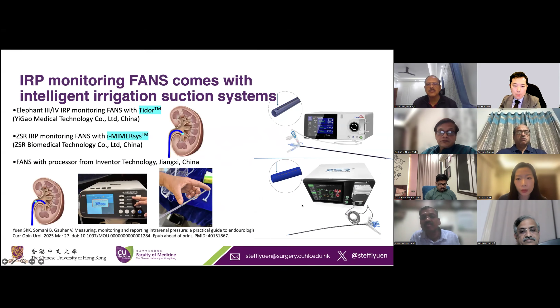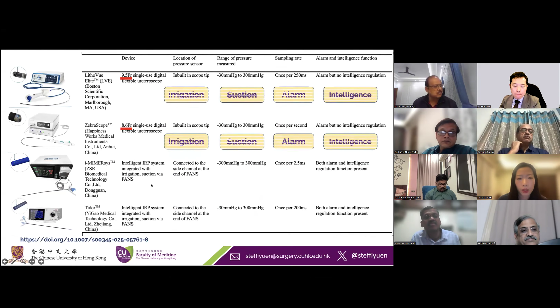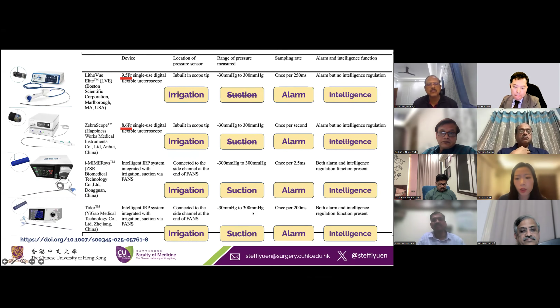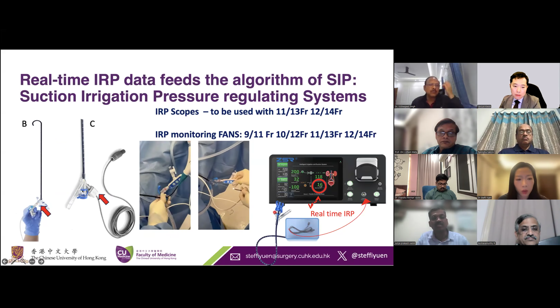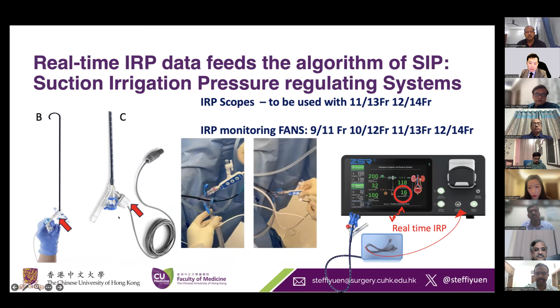There are different configurations of these pressure monitoring ports and also mechanisms, causing maybe very slight differences in the pressure monitored. But in essence, if it's scope based, you can only have irrigation through the working channel, and you have an alarm. But with the integrated systems, it can incorporate suction and intelligence because it can modulate the suction and irrigation. Probably we will have more information from the other lectures in this webinar. So apart from the well-known suction port, there's an extra port that we connect the intrarenal pressure sensor to, which is connected to the system.